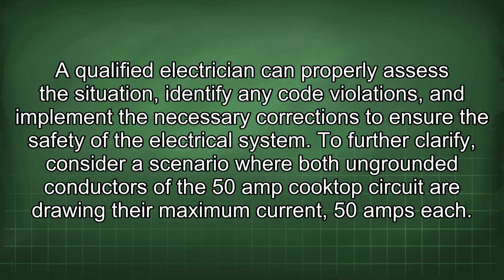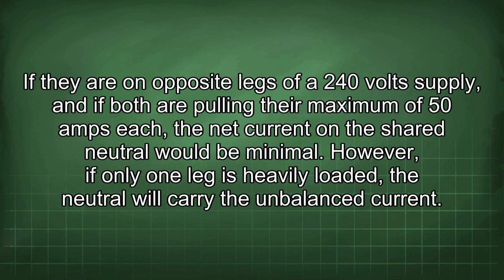To further clarify, consider a scenario where both the ungrounded conductors of the 50-amp cooktop circuit are drawing their maximum current, 50 amps each. If they are on opposite legs of a 240-volt supply, and if both are pulling their maximum of 50 amps each, the net current on the shared neutral would be minimal. However, if only one leg is heavily loaded, the neutral will carry the unbalanced current.